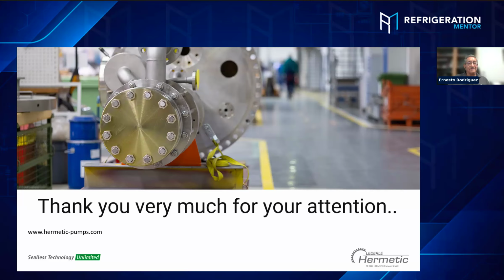What else? You have filters for ammonia. I recommend that you run the filter only for 72 hours for ammonia, because all the oil is removed by the filter. Keep the filter, but remove the mesh after 72 hours. For CO2 it is different. For CO2 you can run it all the time, but the best way is to keep a differential pressure gauge to see the differential pressure across the filter. One more point: check that the thermistors are connected. The pump has a thermistor, so check it is connected, and check the calibration of the pressure stat or the PLC.